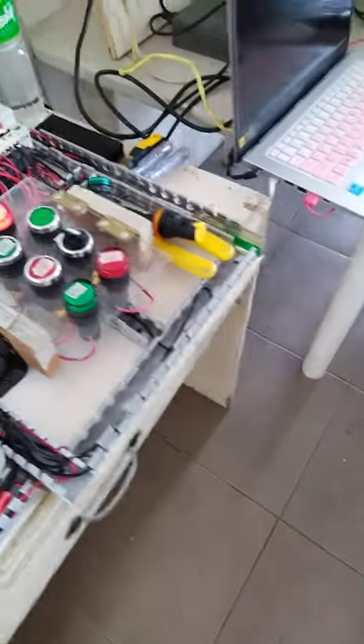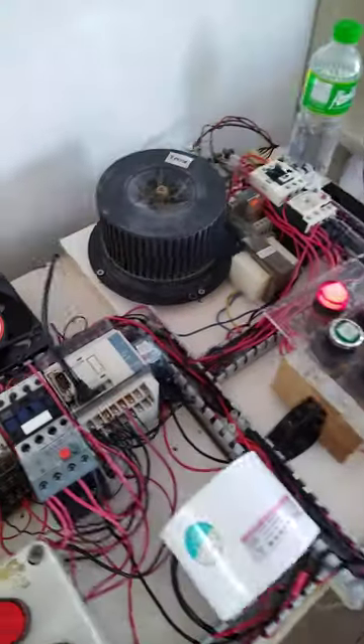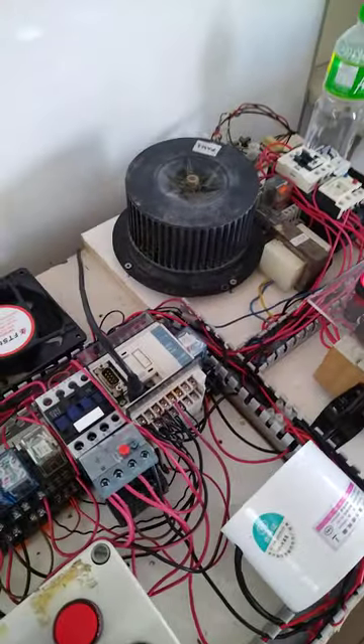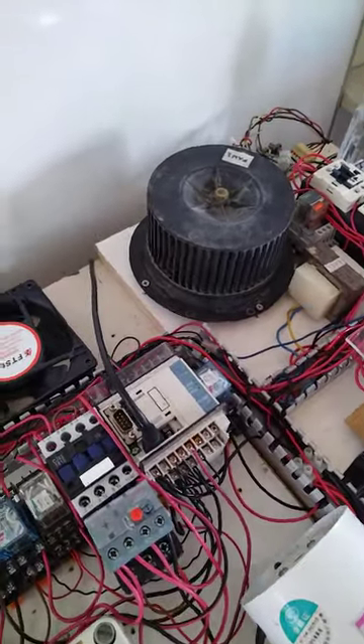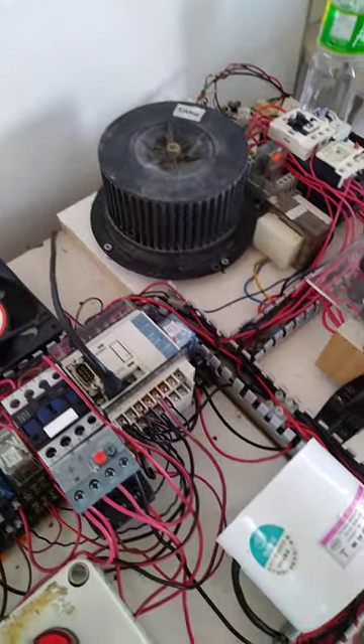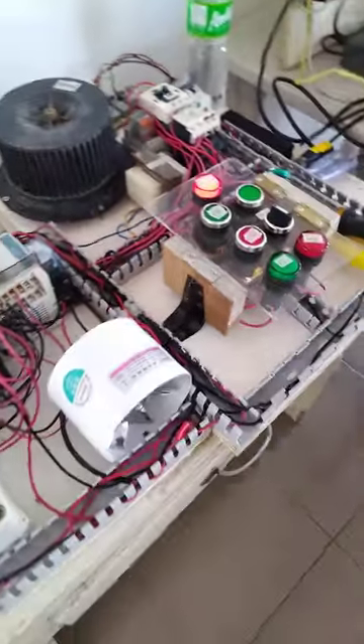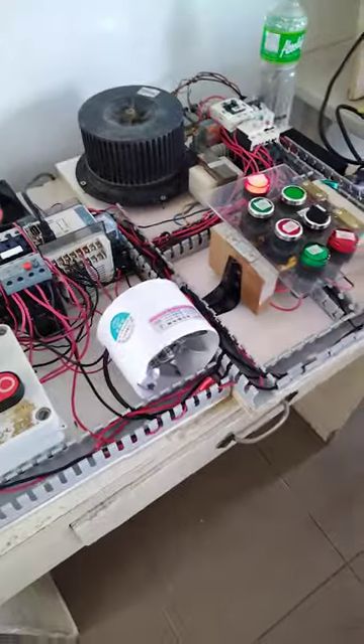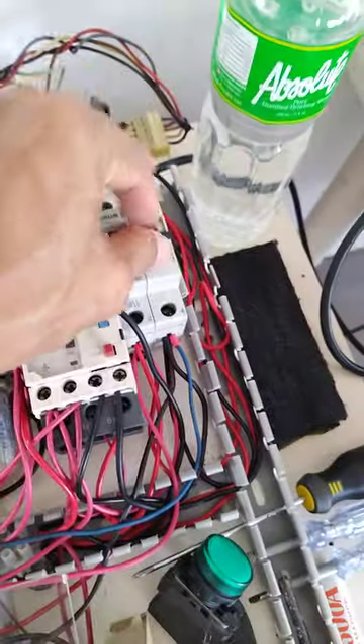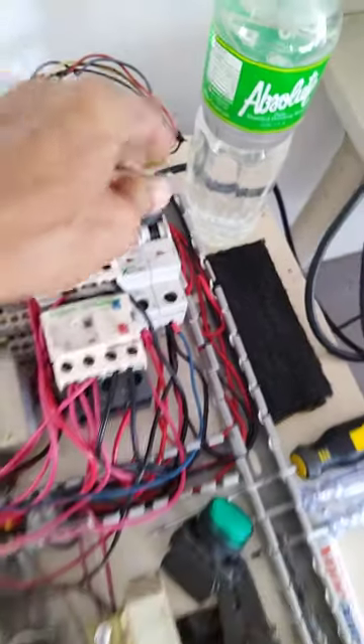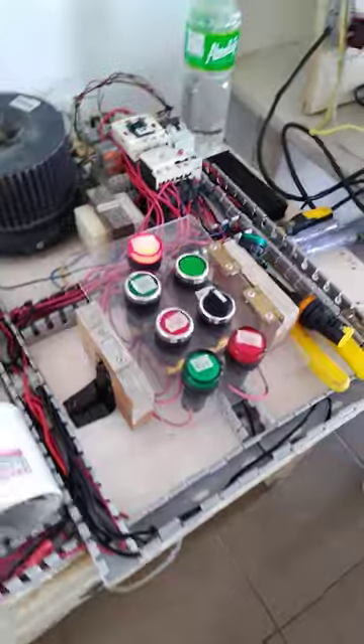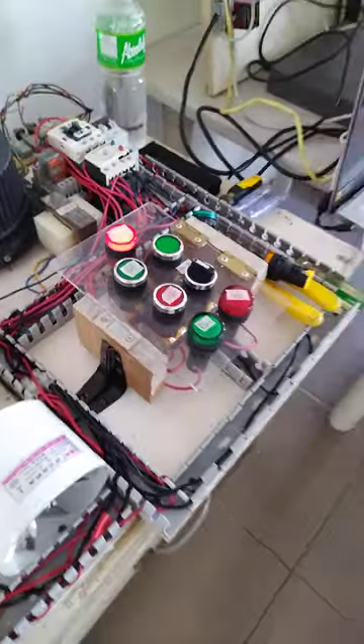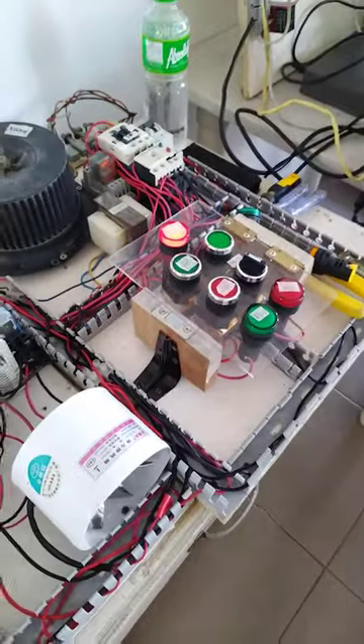I'm just giving a scenario to these guys. I'm telling them that in a building or in a process plant, sometimes you cannot start all fans in one time, I mean simultaneously. For the reason that maybe our circuit breaker will not be able to handle the inrush current when all these big fans are starting at the same time.